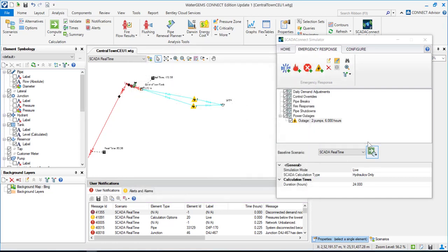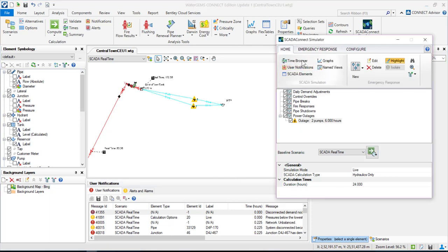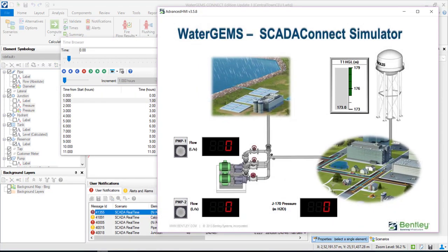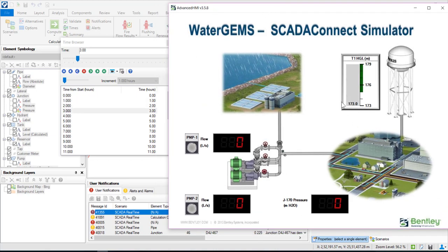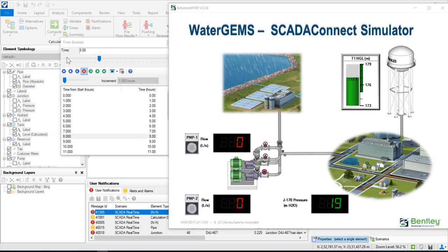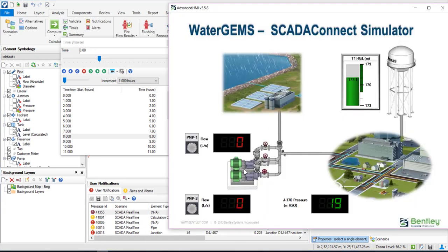You can see that until 6 o'clock in the morning there are warnings and issues that need to be resolved; for the rest of the day it seems okay. These results need to be shown to the operator. Once I hit Compute, the operator will understand that for six hours in the morning there is no water filling the tank. At 6 o'clock both pumps should turn on — the operator might think only one pump is needed, but the hydraulic model indicates both pumps are required.